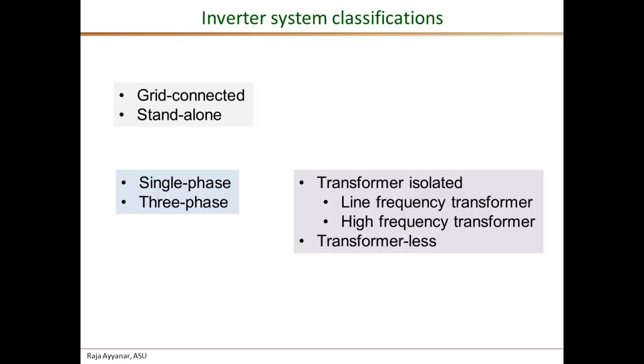Inverters can also be classified based on transformer isolation. Most PV inverters have transformer isolation in some stage — it could be a line-frequency 60 Hz transformer, mostly in utility-scale inverters, or a high-frequency transformer mostly in residential applications. A recent trend in residential rooftop inverters is to go for a transformer-less non-isolated solution, which is supported by standards and codes, requiring operation with ungrounded PV arrays.